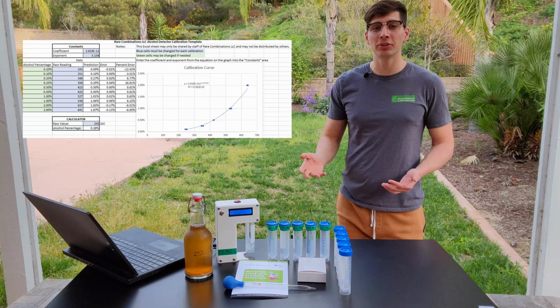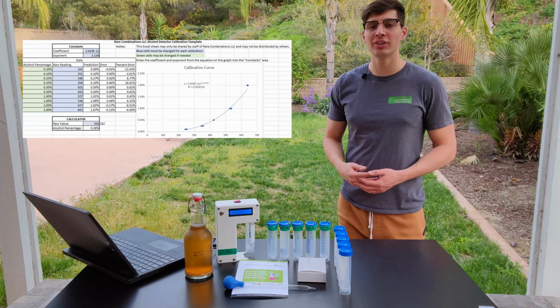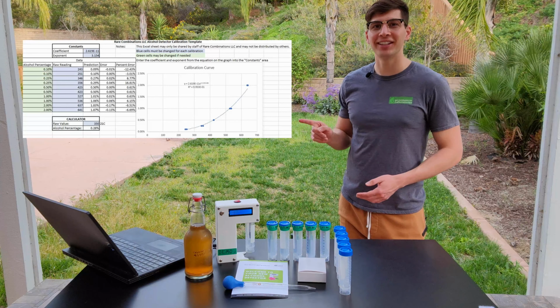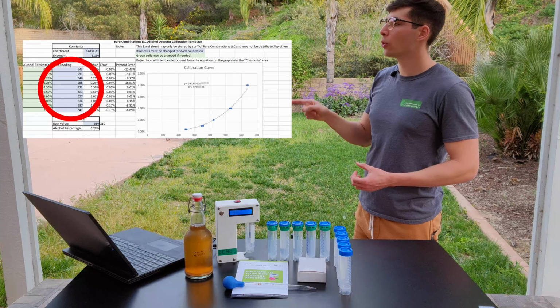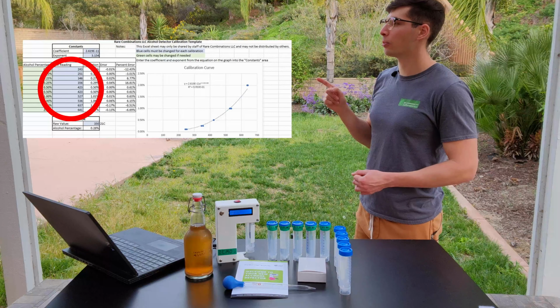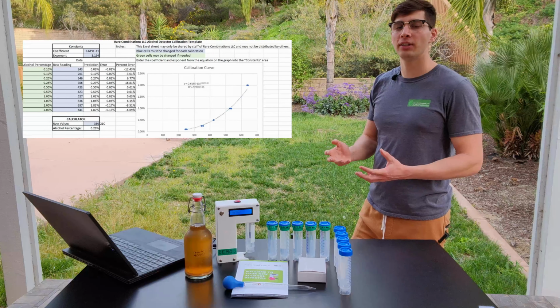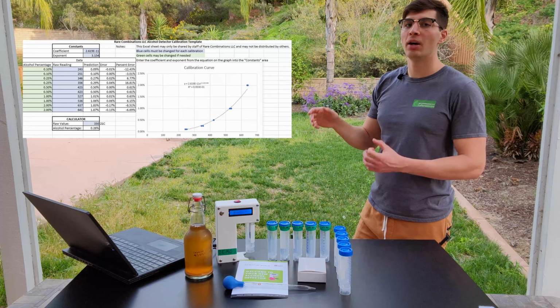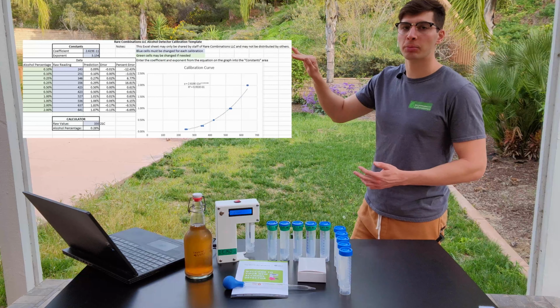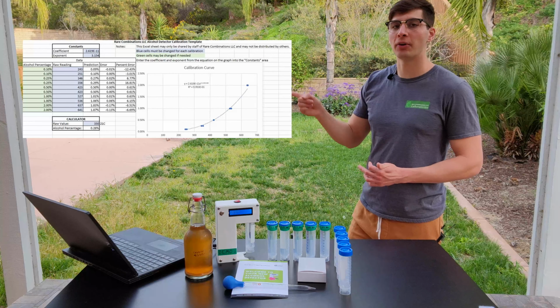It's really simple to use. You don't have to be an Excel wizard. You just have to enter in a few numbers. As we measure our alcohol content standards, we'll enter our values in the blue column corresponding to each of the alcohol percentages. After we enter in all of our known alcohol content standards and their raw readings in the blue column, we should have a smooth calibration curve generated in the graph on the right.